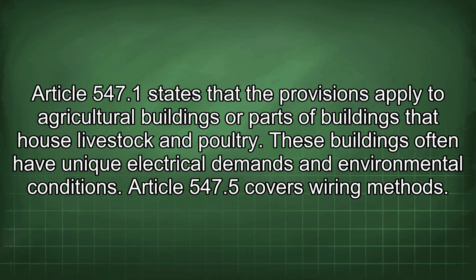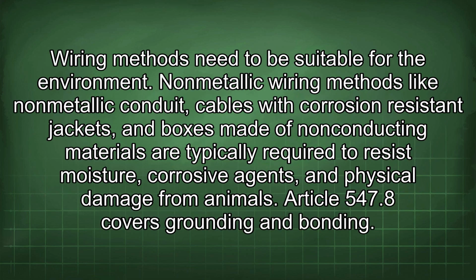Article 547.5 covers wiring methods. Wiring methods need to be suitable for the environment. Non-metallic wiring methods like non-metallic conduit, cables with corrosion-resistant jackets, and boxes made of non-conducting materials are typically required to resist moisture, corrosive agents, and physical damage from animals.